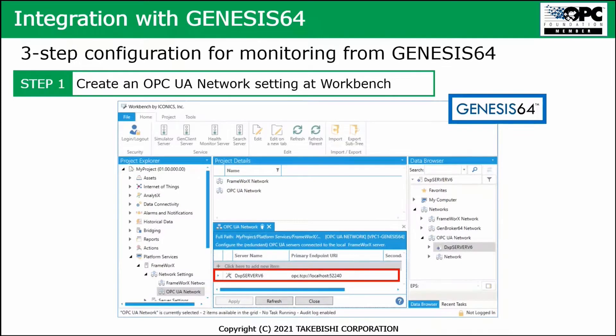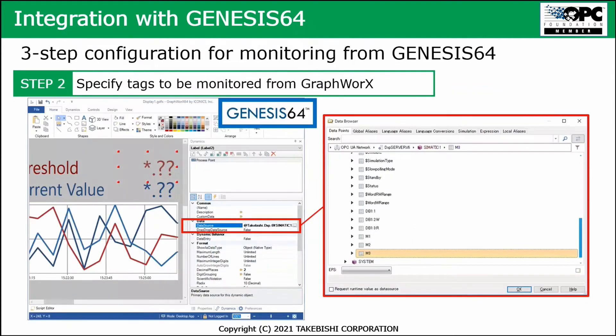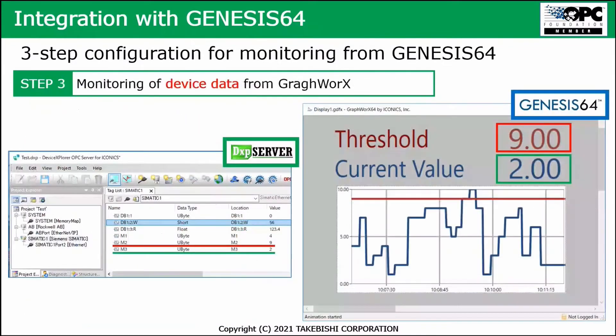Once the process is in operation, you also need a three-step configuration to monitor using Genesis 64. The first step is to create the OPC UA network setting in Workbench within Genesis 64. The second step is to specify which tags you want to monitor from the GraphWorX environment. The third step is to specify and monitor the device data from GraphWorX, where you can see thresholds and values of different tags.